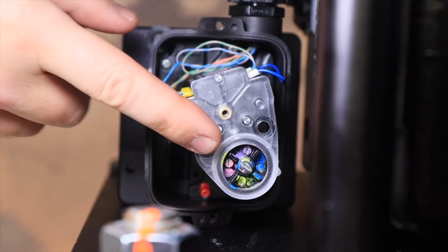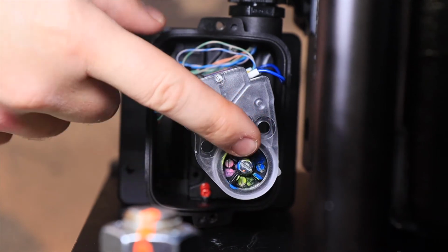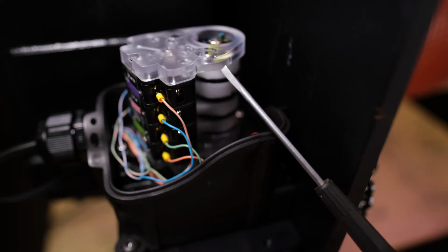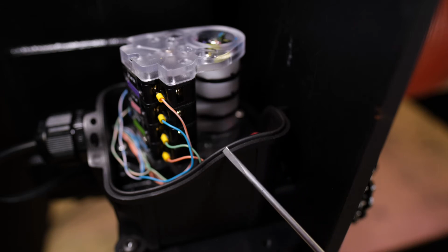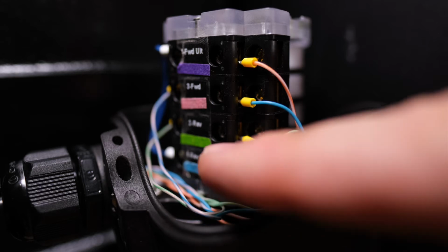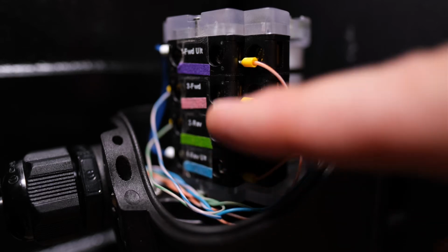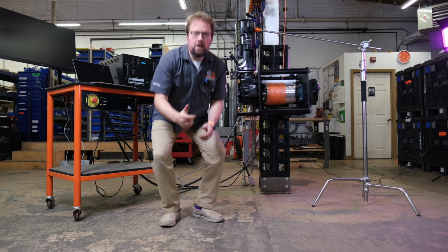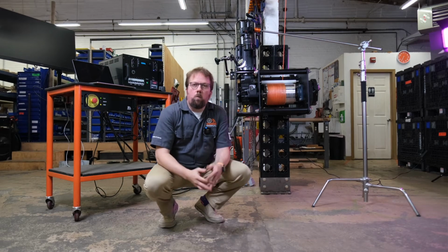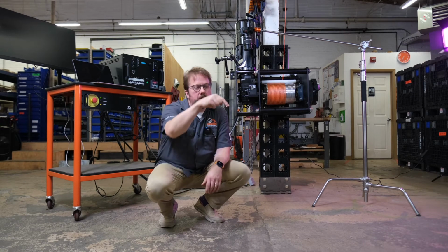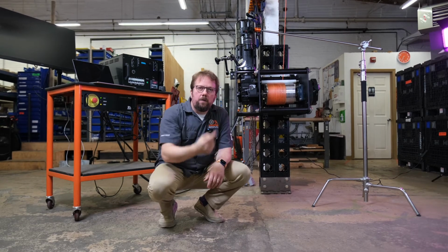With the cover off, we can see that there is a cam stack and a series of micro switches, each of which get independently struck by a cam in the stack. At the bottom, we have reverse ultimate, and then we've got reverse initial, forward initial, and at the top, forward ultimate. Now, you can reasonably ask, why do we need 4 limit switches? Wouldn't 2 be enough? Don't we just need one down and one up?